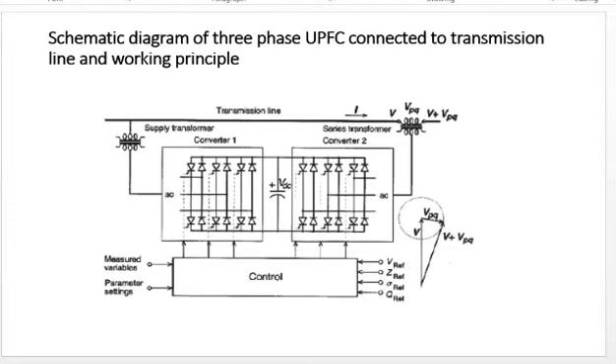which the active power can freely flow in either direction between the AC terminals of the two converters. Each converter can independently generate or absorb reactive power through its own output terminals. One voltage source converter is connected to the transmission line via a shunt transformer, as we can see here.